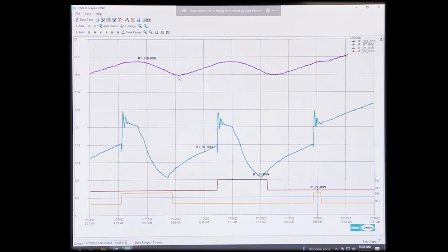Okay, I'll back up the trend log because everything's here and I'll show you exactly when that happened, all right? So in this particular trend log, under Rink Trend, we're looking at 4 things. We're looking at the slab reading, which is in purple, and we're looking at the return reading, R1, return reading, which is this green line here. This is our return glycol temperature.